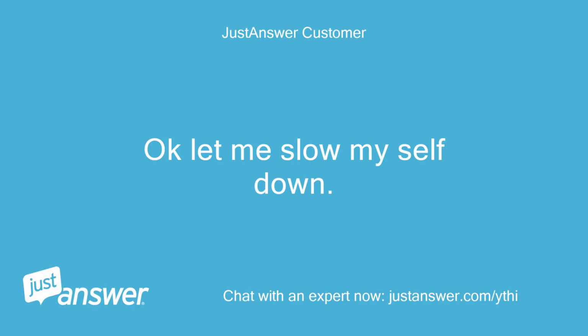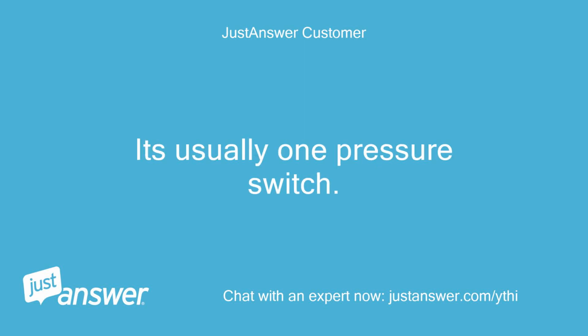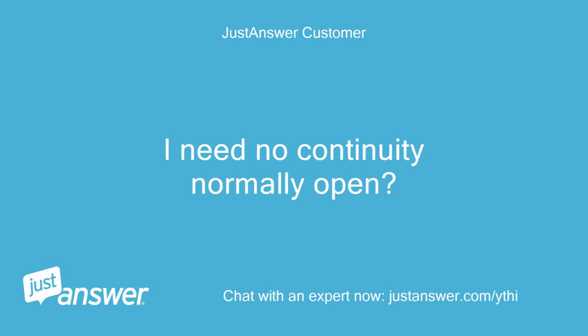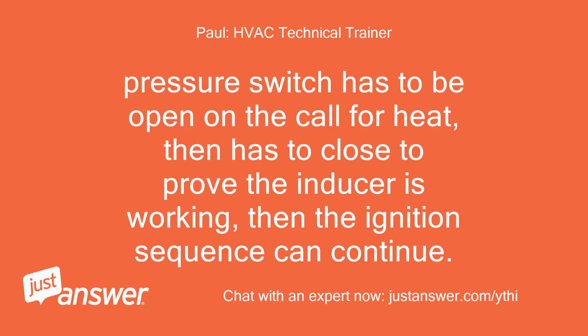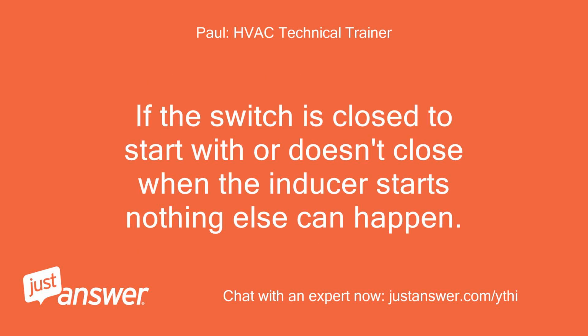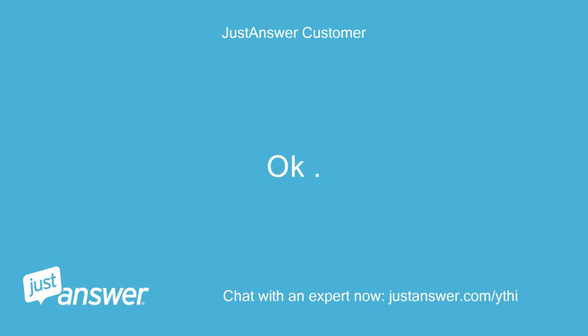Okay, let me slow myself down. It's usually one pressure switch. I need no continuity, normally open. The pressure switch has to be open on the call for heat, then has to close to prove the inducer is working, then the ignition sequence can continue. If the switch is closed to start with or doesn't close when the inducer starts, nothing else can happen. Okay.